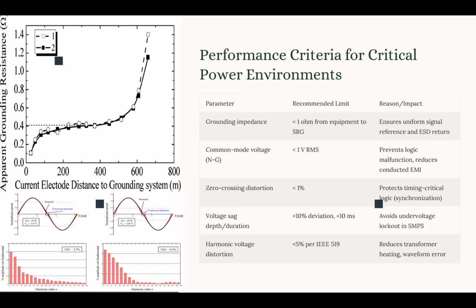The limit recommended for sensitive equipment by IEEE 1100 is that distortion should be less than 1%. We are going to use the THD formula to measure that distortion. But the window is not the full cycle, it is limited to the interval when the waveform is crossing the zero value.